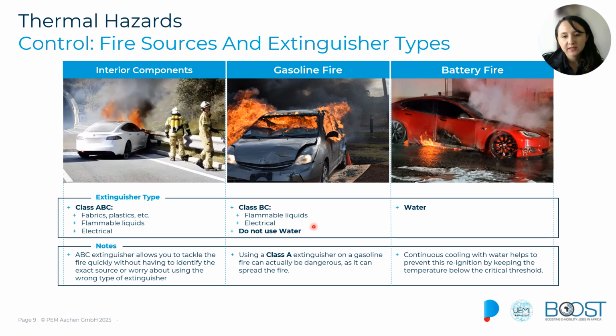On the other side, class BC extinguishers are specifically targeted for flammable liquids as well as electrical fires. Finally, water is one of the best approaches for battery fires. In those cases, we use a large amount of water to cool down the battery, prevent further thermal runaway, and reduce the risk of reignition as thermal runaway expands through the battery cells.